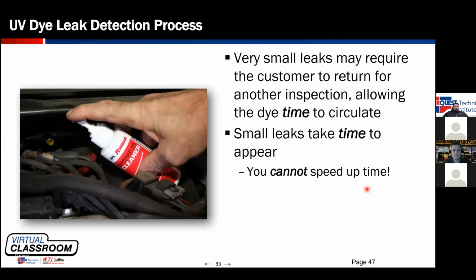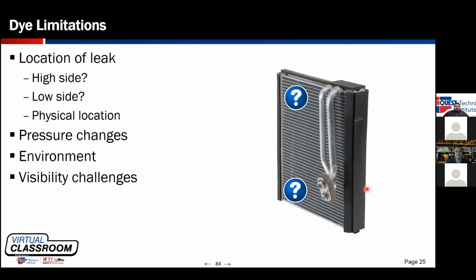Again, once you put dye in, once you find your leak, clean it up. Clean the dye residue off of the surface. There are some limitations to dye. Dye is a great thing. If you have dye on a component, it means you have a leak. But just because there is no dye on a component doesn't mean that you don't have a leak there. Depending on where in the system the component is, it may not show dye.